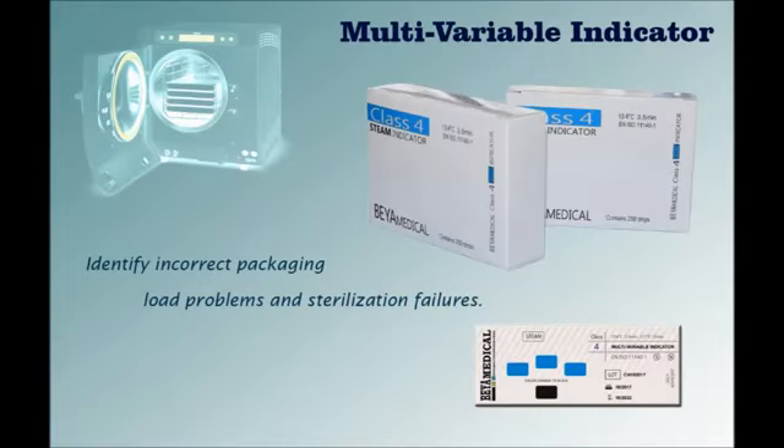BEYAMEDICAL Multivariable Indicators Class 4 is the best type of chemical indicators. The parameters on the indicator allow us to assess the sterilization process. We can easily understand whether the sterilization process was achieved or not according to the result of the indicator.